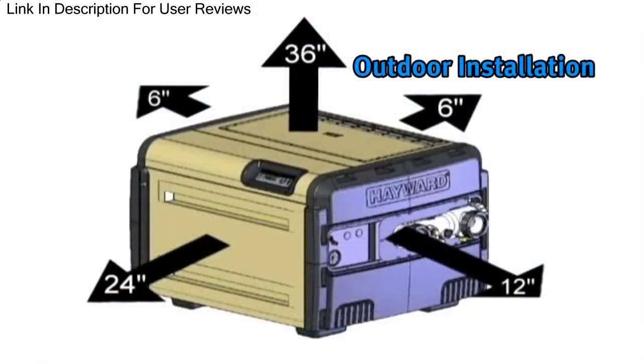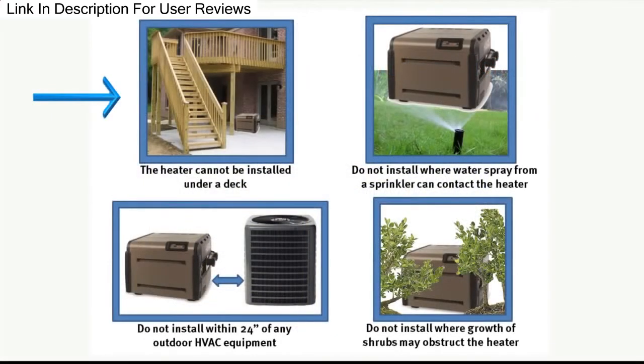If the Universal H Series gas heater is installed outdoors, the heater must have 36-inch clearance over the top, 24-inch clearance in front, 6-inch in back, 12-inch on the water connection side, and 6 inches on the side opposite the water connections. The heater cannot be installed under a deck. Do not install where the water spray from a sprinkler can contact the heater. Do not install within 24 inches of any outdoor HVAC equipment. Do not install where growth of shrubs over time may interfere with the clearances stated in the manual.